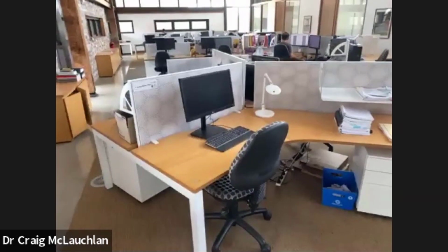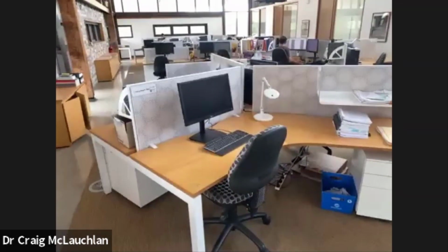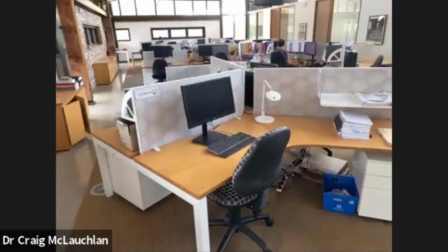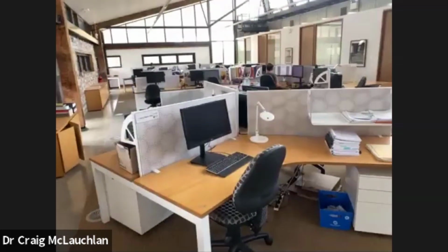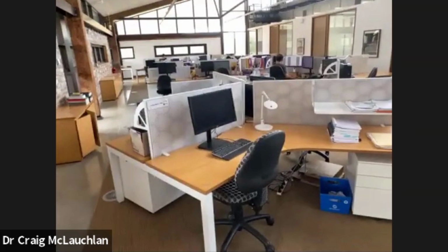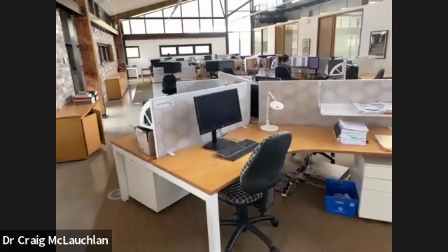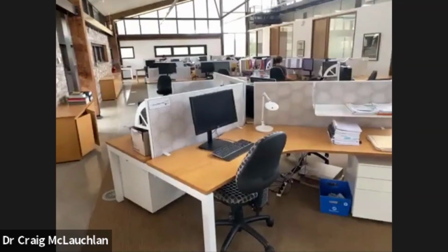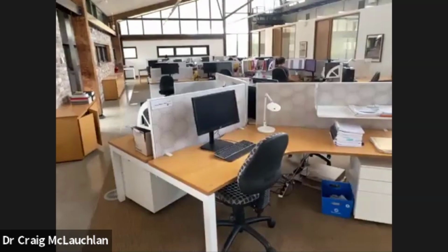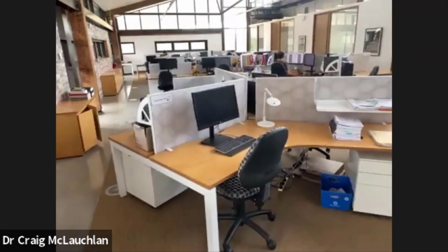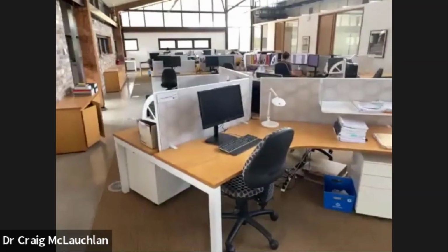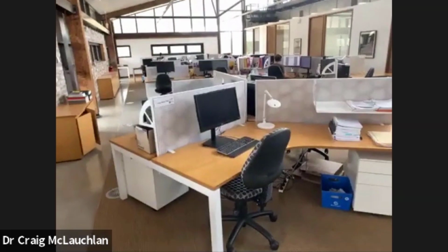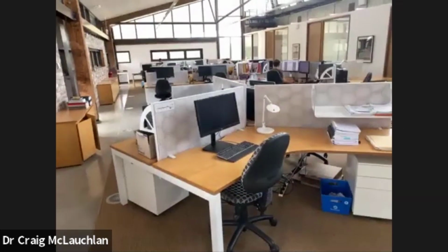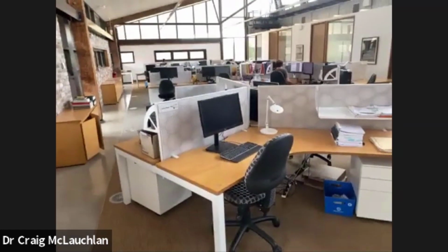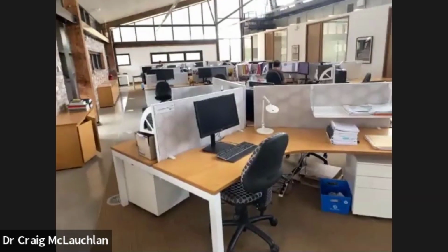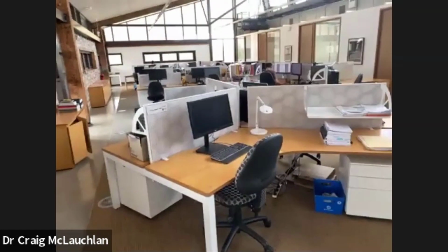What that's done is take the box off the desk, which in reality is probably a 200-watt heater, with about the same heat load as two people. By moving all of those boxes out of this space, we've reduced the heating load the building has to deal with, particularly in summer, which has dropped the air conditioning load, the size required of the air conditioning system, the pipes, the heat pumps, the whole lot. So by simply asking, do we really need that piece of IT equipment, can it be done in a slightly different way, we've reduced the heat load, the aircon plant size, and the energy demand of the building, which has all gone into reducing the size of the PV array needed to be net zero energy. That's just an example of how simple to say, yet profound in effect, that needful use, efficient use, and harvesting can be.